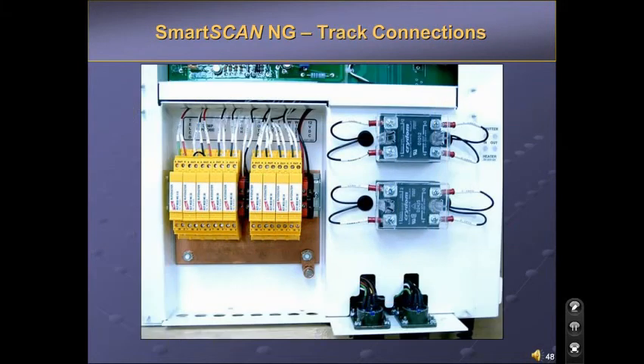To improve the surge protection of the system, the NG system has a built-in Faraday cage. Each line coming in from the track goes through a universal transient barrier, or UTB. This includes the transducers, track circuit wires, auxiliary alarms, telephone line, and temperature probe. The UTBs are closed-circuit devices. If you measure the resistance across one, input to output, and it is open, then it is bad or has been blown. Since we provide inputs for multiple auxiliary alarms, there will normally be a couple of UTBs that are not utilized and can be used as spares.